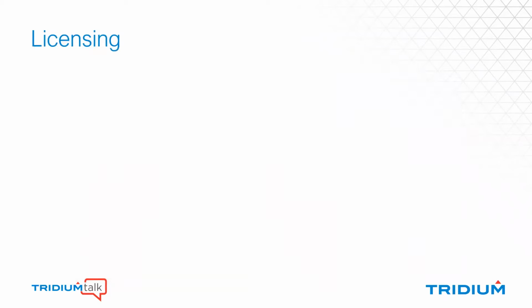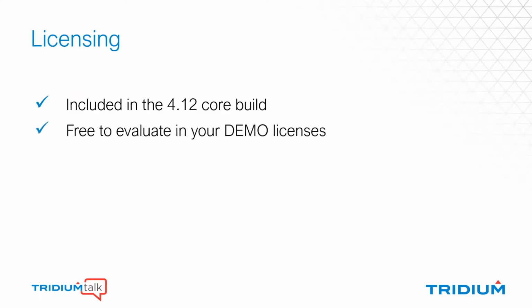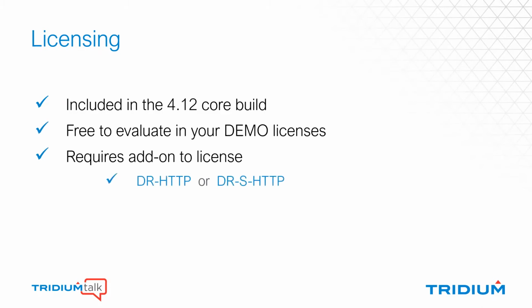One last thing from me, and that's covering the licensing for this. So the HTTP client driver, how many times did I say that, is included in the 4.12 core build. It's free to evaluate in your demo licenses, but requires an add-on to license in your station. So if you are using it in a live building, you'll need to purchase the DR HTTP for an embedded controller, such as a JACE or portability device, or DRS HTTP for a supervisor. It does require active SMA, and this is something that is really key.